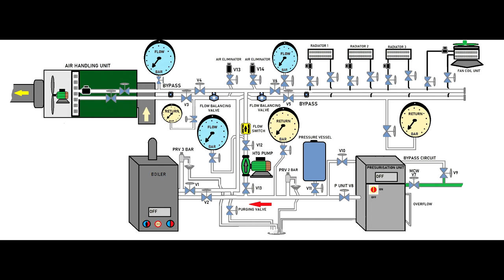Now let's begin. As you see here in this project, I just fitted a kind of drain valve, a purge valve, which allows me to take the air out of the system when I'm filling the system for the first time. You will see it's a red arrow to the bottom. That is very important for me because I fill the system faster than using any other option, so this will be always part of my design.